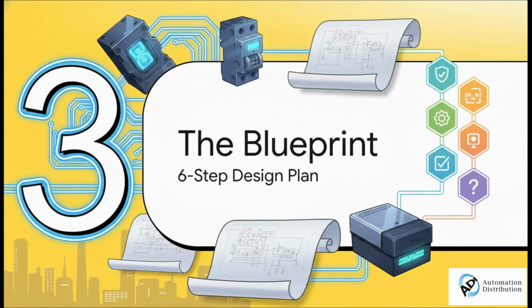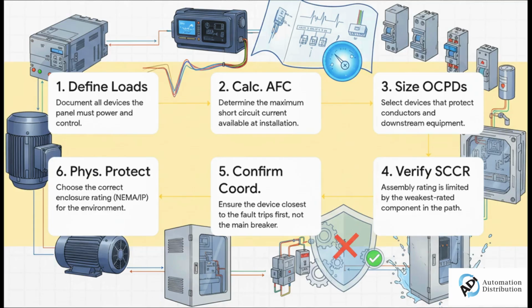So, we know the threats and we know the tools. How in the world do we put this all together? Well, let's move on to the blueprint, a clear, step-by-step process to make sure your design is both safe and compliant. Here's the roadmap, and it all starts with the basics. Step 1, define all your loads. You need to know exactly what you're powering, from your PLCs and drives to every single motor. Second, you have to calculate the absolute worst-case scenario, what we call the available fault current at the site. It's only after you know that in step 3 that you can even begin to size your protective devices to match those loads and keep the wiring safe.